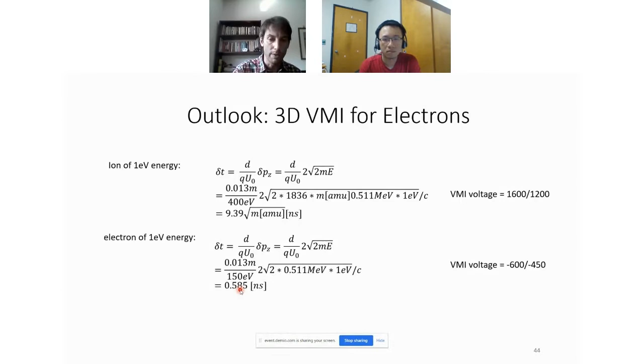But we have made use of a new feature in a new version of the camera, which is that there are now two TDCs. And those two TDCs both have 1/4 of a nanosecond, or 250 picosecond, timing resolution. And so what we do is we capacitively couple to the phosphor screen of our detector, go through a constant fraction discriminator, and feed that information into TDC number 2. There's a photodiode, or a delay generator synchronized with the laser, that goes into TDC number 1.